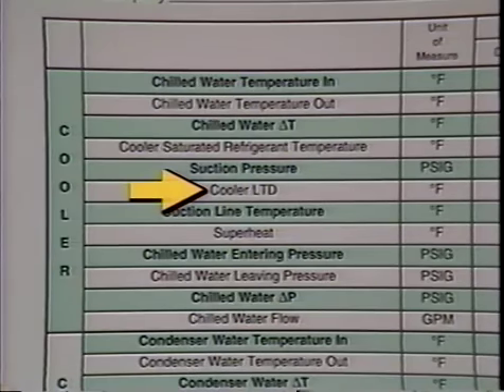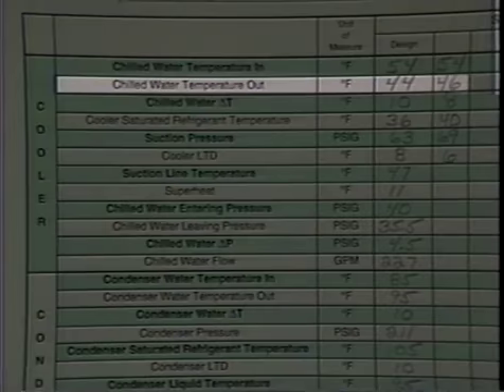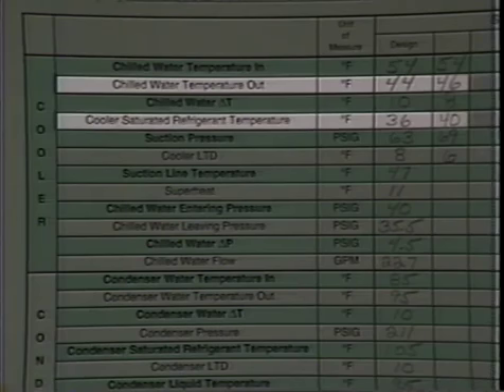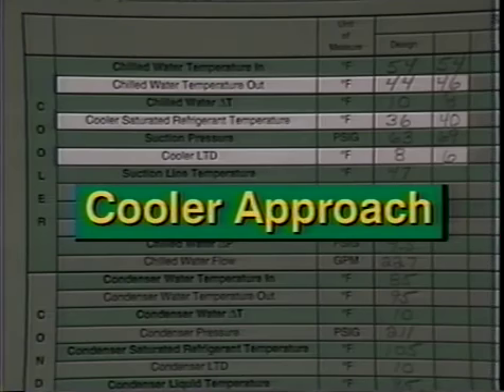Cooler leaving temperature difference, LTD. At this point, we can calculate the cooler leaving temperature difference, LTD. This is the difference between leaving chilled water temperature and the saturated refrigerant temperature. This difference is also known as the cooler approach.